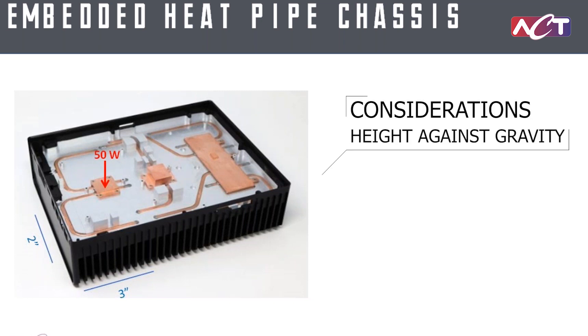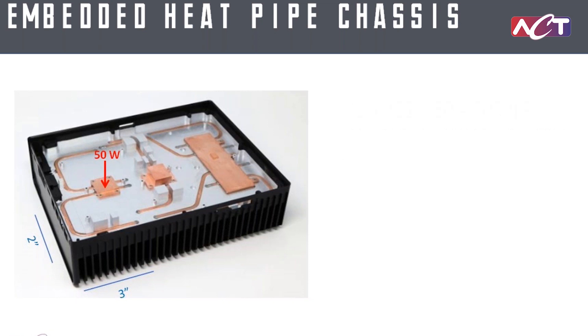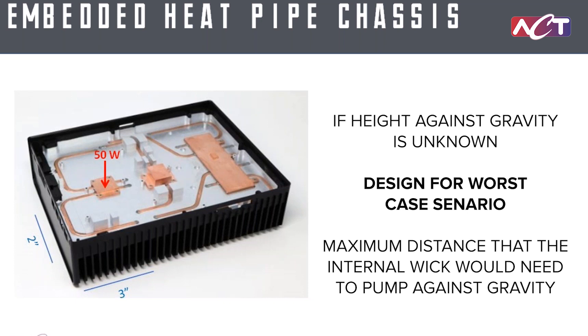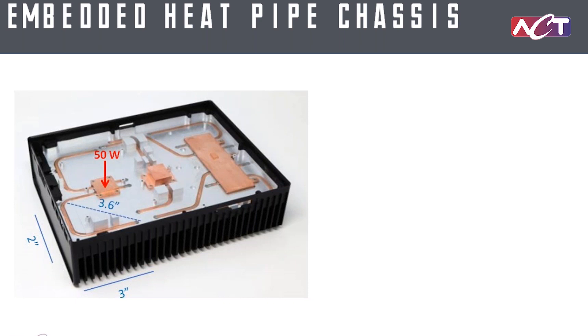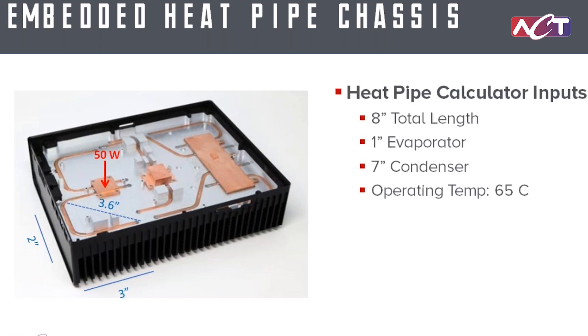The next step is to figure out the height against gravity — this is probably the most complex consideration with this type of geometry. If the system were sitting flat on a table, the height against gravity would be zero. But if it's going into a system where you don't know the orientation, you have to design for worst case. You need to find the maximum distance in the U that the wick structure would need to pump against gravity — in this case that's the diagonal section, about 3.6 inches.